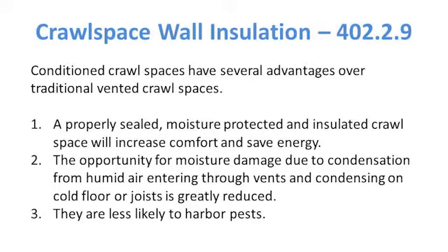Conditioned crawl spaces have several advantages over traditional ventilated crawl spaces. Number 1, a properly sealed, moisture-protected and insulated crawl space will increase comfort and save energy. Number 2, the opportunity for moisture damage due to condensation from warm, humid air entering through the vents and condensing on cold building components such as floor joists or the floor system is greatly reduced. Number 3, they are less likely to harbor pests.